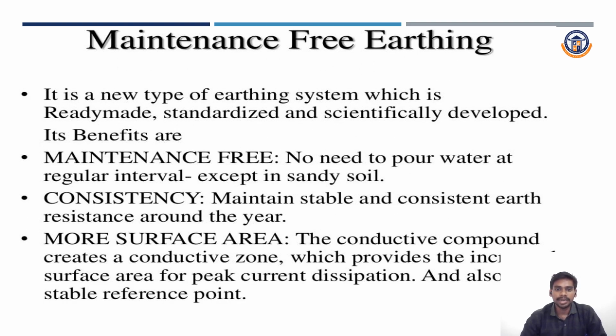Next one is maintenance free earthing. It's a new type of earthing system which is ready-made, standardized and scientifically developed. Its benefits are maintenance free: no need to pour water at regular intervals except in sandy soil. Consistency: it maintains a stable earth resistance all around. More surface area: the conductive compound creates a conductive zone which provides an increased surface area for fault current dissipation and also a stable reference point.